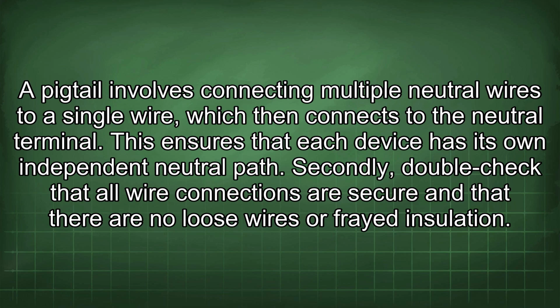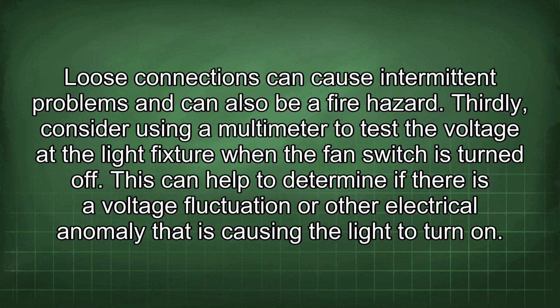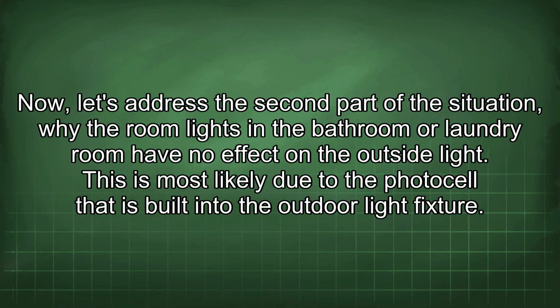Secondly, double-check that all wire connections are secure and that there are no loose wires or frayed insulation. Loose connections can cause intermittent problems and can also be a fire hazard. Thirdly, consider using a multimeter to test the voltage at the light fixture when the fan switch is turned off. This can help to determine if there is a voltage fluctuation or other electrical anomaly that is causing the light to turn on. Now, let's address the second part of the situation, why the room lights in the bathroom or laundry room have no effect on the outside light.